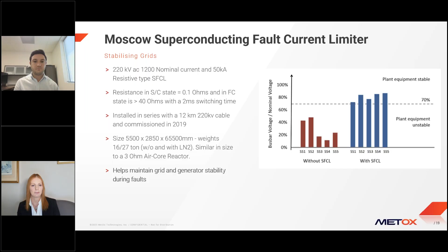This was installed in 2019. One of the key things they were trying to do was avoid big voltage reductions during faults. In this chart, the blue columns represent retained voltage during a fault, showing how much of that voltage is retained. It's important to keep retained voltage levels high to avoid interruptions to industrial processes, or causing generators in the area to go unstable. That's one of the big use cases for the Moscow superconducting fault current limiter, which has been in service since 2019.